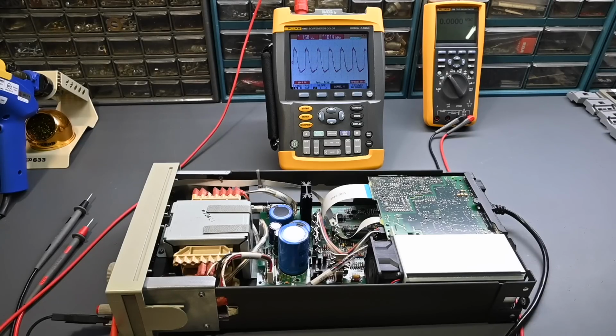Now remember, this is not a switching power supply, so to see 100 kilohertz of some kind of a ripple sort of a voltage that's coming out of the power supply, there's no high frequency switching that should be going on in this power supply. So it's a 60 hertz transformer, a linear type regulator. It should be a very noise-free type of output. So a switch mode type power supply, you might expect to see some high frequency ripple and things going on, but certainly not 1.56 volts. So that's way too high on any power supply. And in this power supply, it should basically be noise-free. So yeah, definitely an issue going on with that voltage regulation circuit.